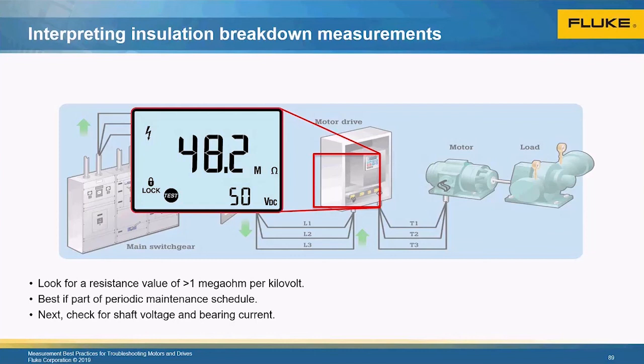So obviously, this is a way of determining how much electrical health is left. And if you think about an insulation tester, this is go, no go, isn't it? If I get a low reading here, now's my idea to take it out of circuit before it dies. And it will die. Now you're on the negative slope of the lifespan of that motor. And we want to catch that before it dies, don't we? Because if it does die and you blow it up, you might not have any life left in it to repair it. We want to be able to repair it still, right? As opposed to destroying it and having to replace it with a brand new one.